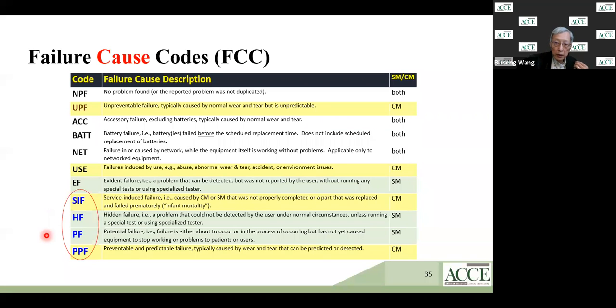Okay. Potential failure is something that is in the process of happening, like a power cord that is fraying but has not completely shorted out. And if you detect that, you need to correct that. And this is by far the most important one that we want to avoid. We want to reduce the probability of happening; it is a preventable and predictable failure. Sometimes wear and tear was not predicted or suggested by the manufacturer, and we found out later that using a device in, for example, an environment that is very dusty or where the power line fluctuates a lot, you have a lot of problems. So we really need to do something about this as soon as we detect that.